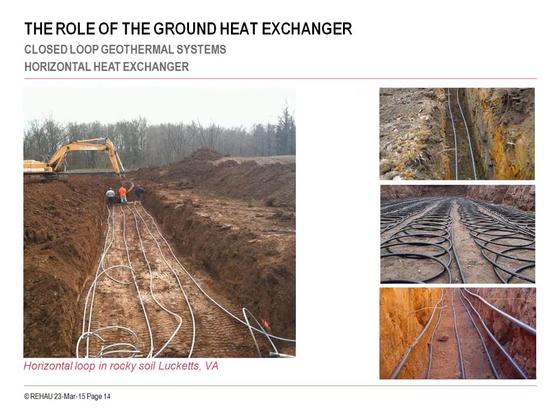Some images on closed loop. On horizontal, that would be a commercial application on the left, down about 7 or 8 feet. We've got 3 circuits of piping running down. There will be a backfill of about 2 feet, and then another set of 3 circuits running down in that trench, and then you would have multiple trenches.